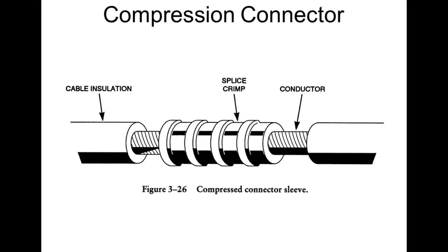Now copper, we don't worry about that. We do this on copper too, but anytime you mix aluminum and copper, make sure you put that stuff on there too. Anytime you splice aluminum, anytime you use aluminum wire and splice it to something or terminate it somewhere, you need to make sure you do what? If you terminate it with these crimp things, you need to make sure you put that antioxidant.